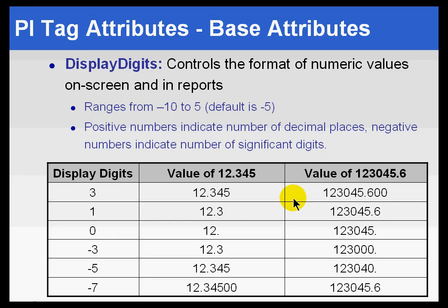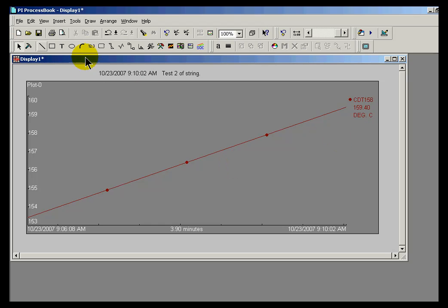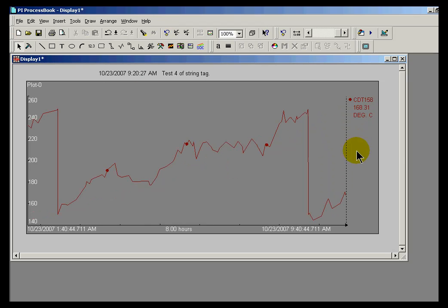The DisplayDigits attribute controls how we display data by default in ProcessBook. You have a field that takes either a positive or a negative integer. Positive indicates number of decimal places; negative indicates significant digits. For example, a positive five would indicate five decimal places for display in ProcessBook. If I look at ProcessBook right now at my PI tag, this is showing as five significant digits, so this is probably set up with a DisplayDigits of negative five.